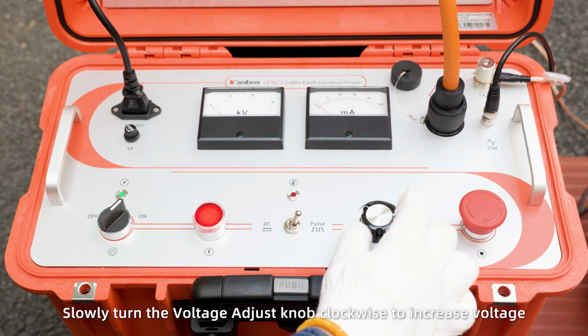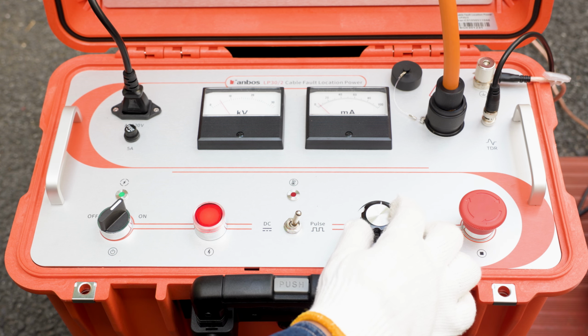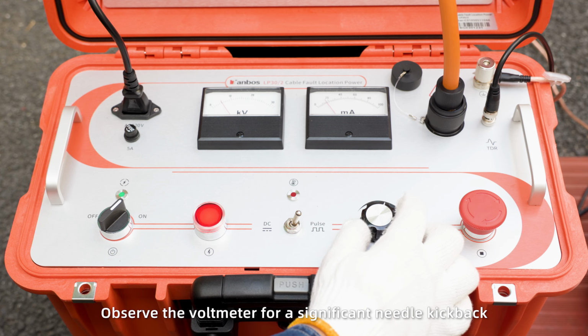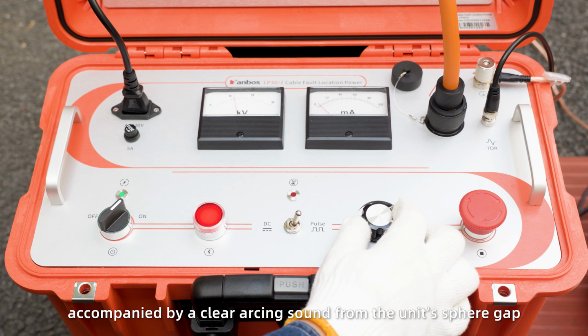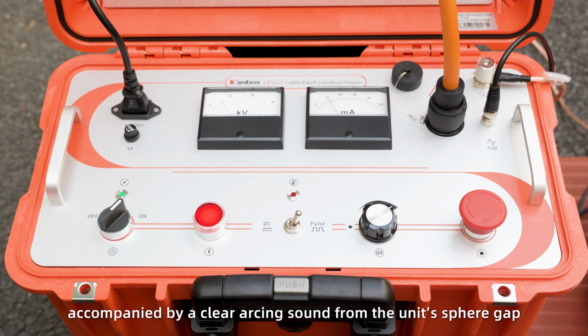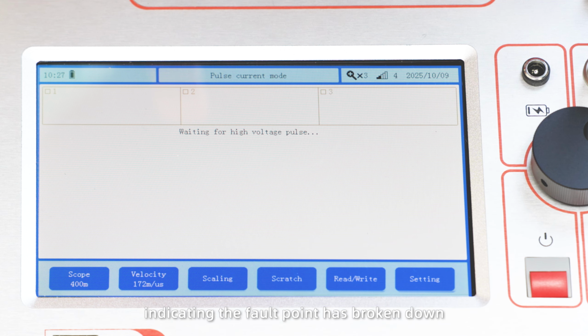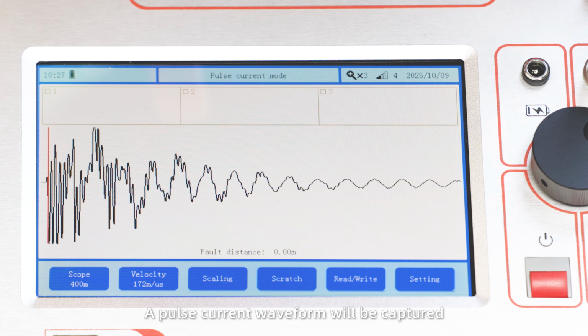Slowly turn the voltage adjust knob clockwise to increase voltage. Observe the voltmeter for a significant needle kickback, accompanied by a clear arcing sound from the unit sphere gap, indicating the fault point has broken down. A pulse current waveform will be captured.